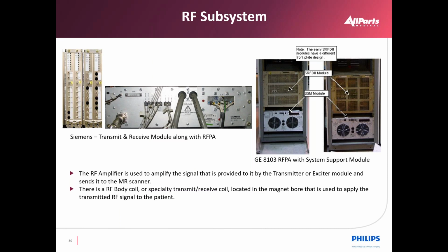The RF amplifiers are used to amplify the signal generated by the transmitter module, which are then sent to the MR scanner. Specialized RF coils, such as body coils or certain head coils, are able to both transmit and receive RF signals and can apply these signals to the patient.